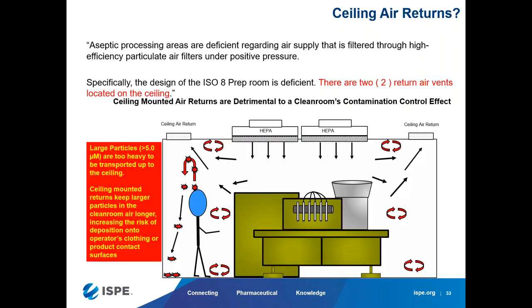The other thing is ceiling returns, that's past century, okay? We are learning all the time. Now this 483 talks about you had ceiling returns. Ceiling returns don't belong in clean rooms, especially not only aseptic, even non-sterile. Why? Because 5-micron particles don't carry so well upward, right? They're heavy particles, 0.5, 0.3 is okay. Where do they hang out? They hang out at work level.